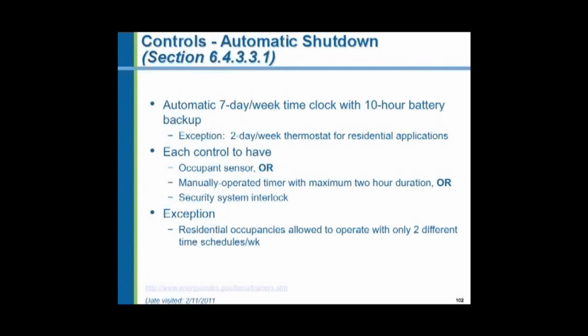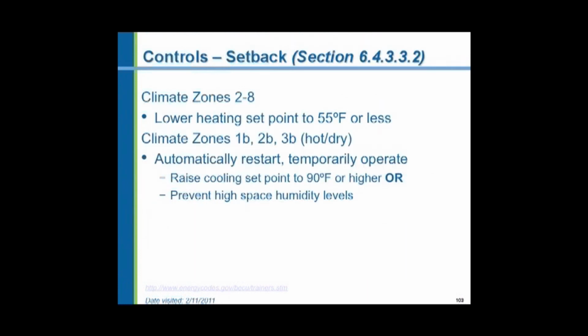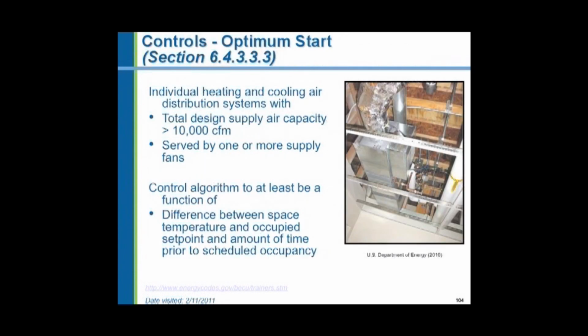Have to shut the systems down with an automatic 7-day time clock. It has to have a battery carryover in case of power failures. Or you could have an occupant sensor. Many of the offices in buildings now, instead of light switches, have occupant sensors. When the occupant leaves the room, the lights go off. And they want us to set the temperature back at night down to 55 degrees or less.